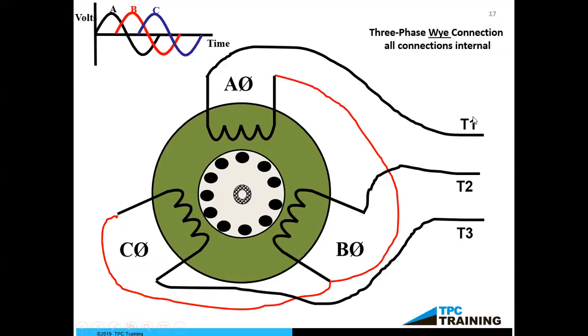So we would do that between T1 and T2. We would get a reading. Let's say the reading is 18 ohms. Then we would go to T1 and T3, and we would want to see that exact same number, 18 ohms. And then we would go between T2 and T3. So we would be checking all three of these windings. We're checking two at one time, but by going between T1 and T2, and then T2 and T3, and then T1 and T3, it would tell me if all my windings were good or not. And if I got 18 ohms on T1 and T2, I better see 18 ohms on T2 and T3, and 18 ohms on T1 and T3.